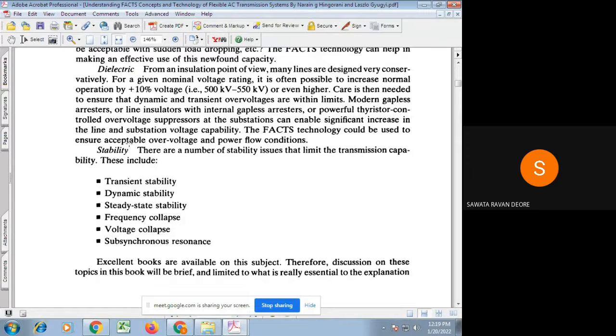Transient stability is nothing but the ability of the power system to remain in synchronism after sustaining a large disturbance. That large disturbance may be a fault, sudden loss of load, sudden loss of generation, or sudden loss of electrical network, that is, one or two transmission lines of the given electrical network. That creates a large mismatch between generation and demand, and the system which maintains synchronism under that condition is called transient stability.